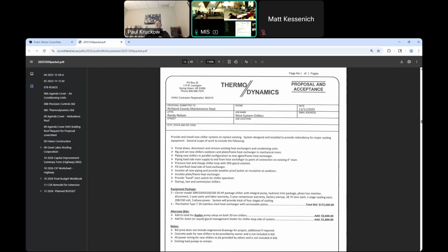One thought would be, and they're slightly different frames. They're all 2 horsepower, but they're slightly different frames. One thought would be, at bare minimum, to have a spare pump on hand. So if the pump quits, you change it out. We really have to look at that a little bit, how the body and frame looks compared to existing, to see if it's, oh well, you just slide it in, or well, we've got to do slight pipe modification to fit it. 2 horsepower pumps aren't large, but there's 3 of them and a very important part of your system. A chiller can run all day, but if the pump dies, you're done. So to me, that is a concern that I had about the project.